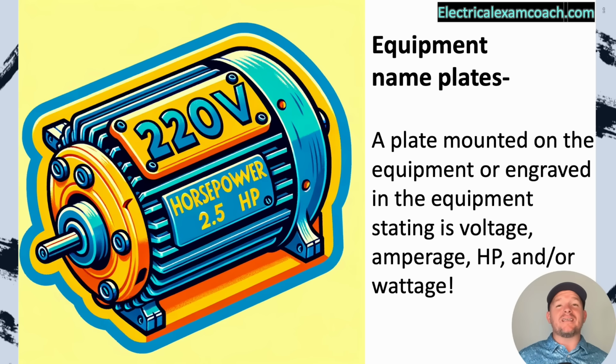And that's where we're going to get our information for our dryers. Thankfully, in electrical exam prep, they're always going to tell you the wattage of the dryer. All you have to remember is that if it falls below 5,000, we're going to use 5,000 as a minimum. And if it goes above 5,000, we're going to use whatever is stated on the nameplate.